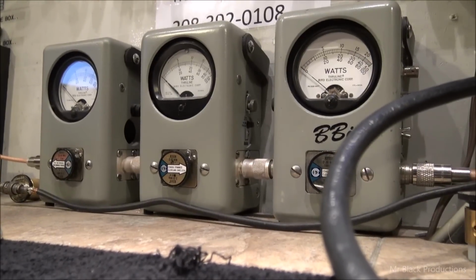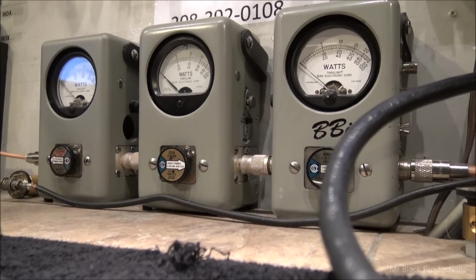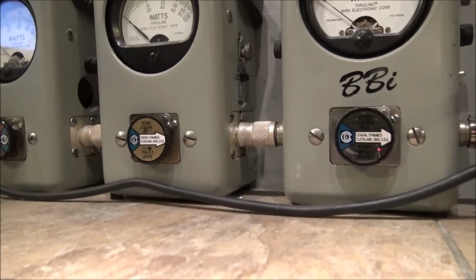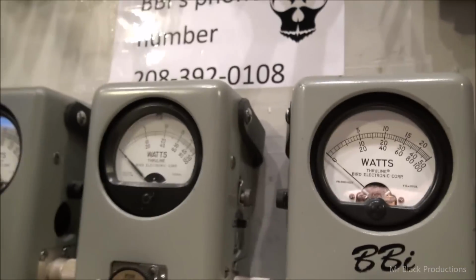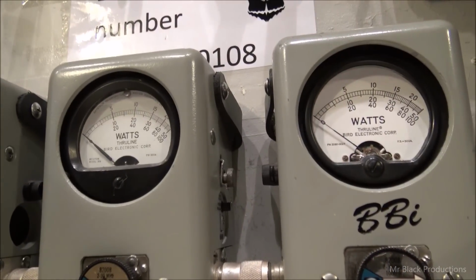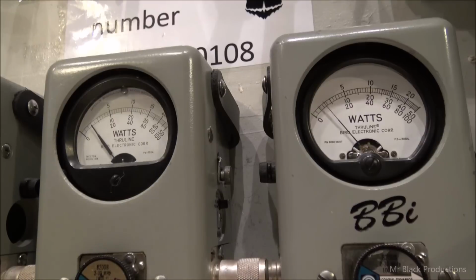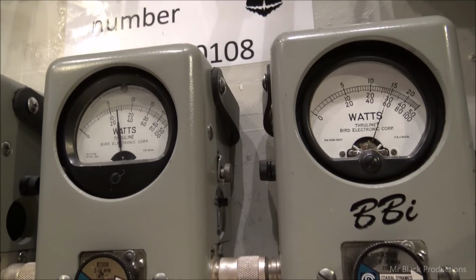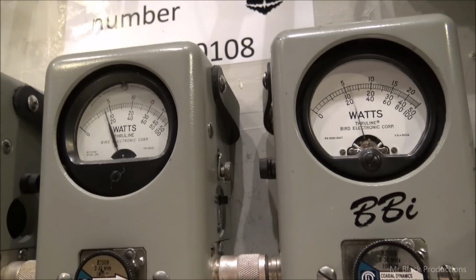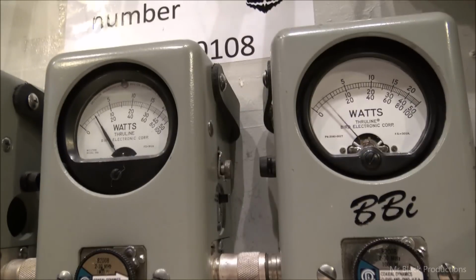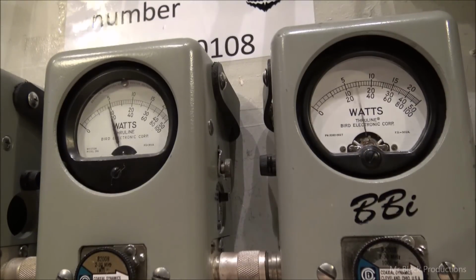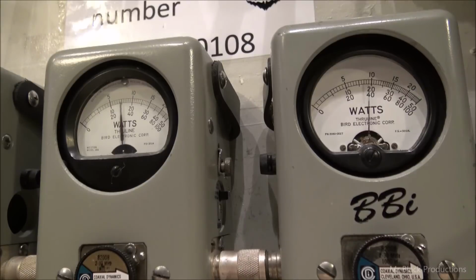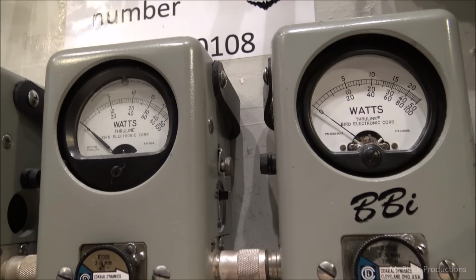And we'll try to swing this up, show the average output power. Hopefully we can do this without tripping the breaker too bad. Now the lights are dimming in here pretty good. And as we come up in drive, you'll see that our peak numbers are falling off.